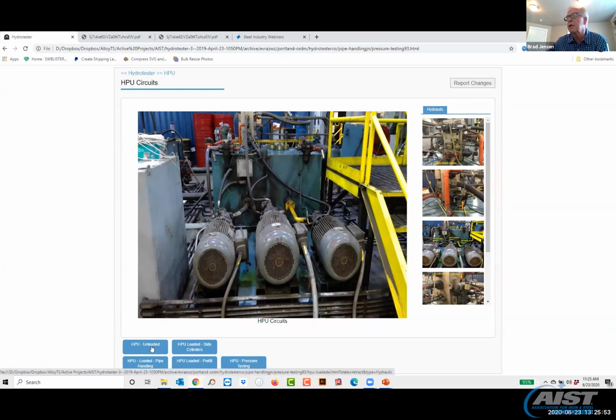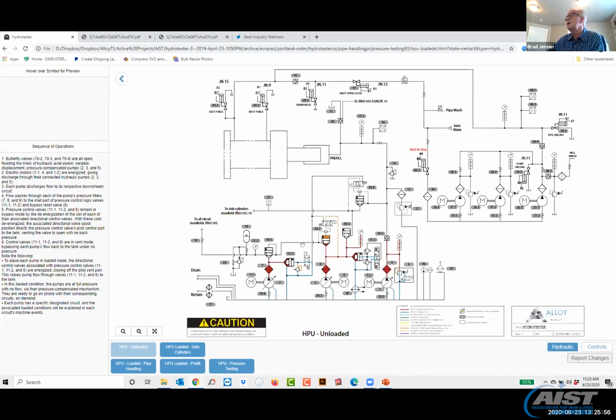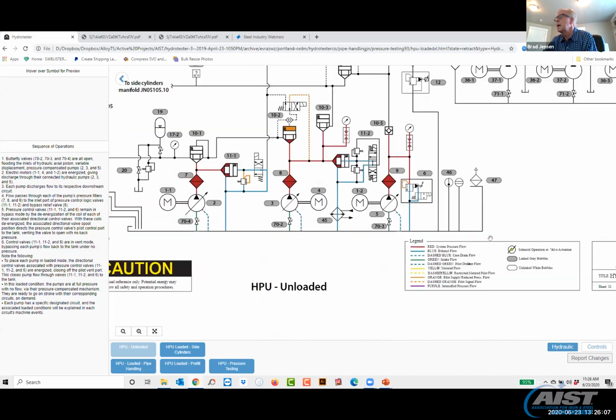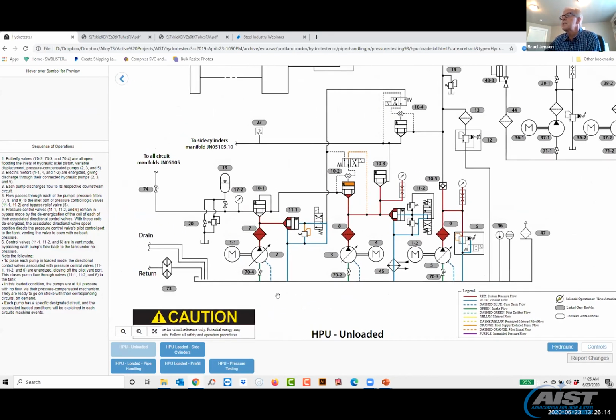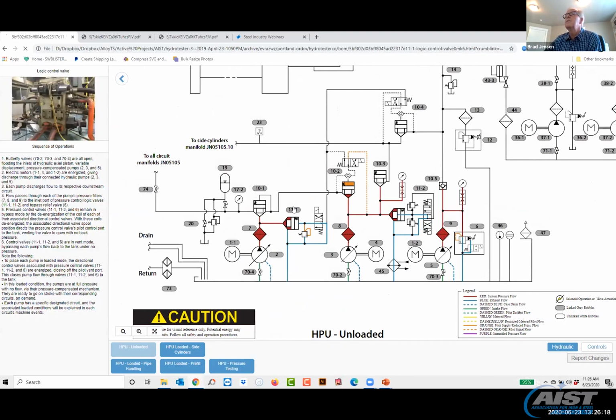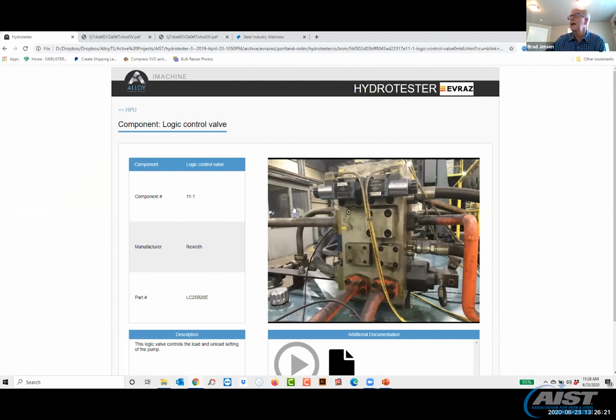But if I go to the unloaded, you can see that we are along the same color coding here of what's happening. But we have a little bit more complicated application, because in this particular HPU, we've got one of those manifolds that have logic valves bolted all the way around it. And again, I can't emphasize how important it is to be able to have a schematic that's accurate, that you can read, so that you're not pulling one of those off, heaven forbid, under pressure, not knowing which one you're on.